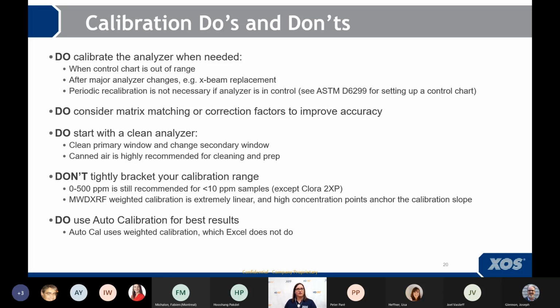Some other things to consider: consider using matrix matching or correction factors to improve accuracy. Some of our customers like to set up gasoline-specific calibrations. You can do that. I'll talk a little bit more later on in the presentation about correction factors. Obviously, you'll want to start off with a clean analyzer. We went through the importance of it being clean, so before you calibrate, make sure you have a clean primary window and you change the secondary window.